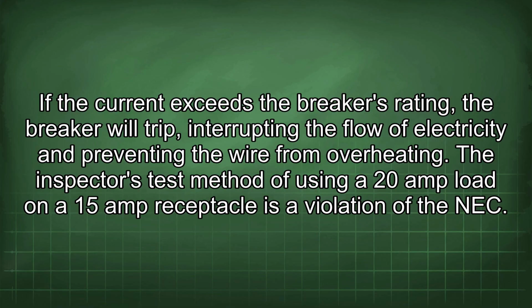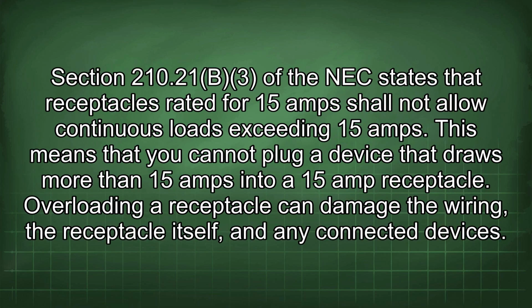The inspector's test method of using a 20 amp load on a 15 amp receptacle is a violation of the NEC. Section 210.21(B)(3) of the NEC states that receptacles rated for 15 amps shall not allow continuous loads exceeding 15 amps. This means that you cannot plug a device that draws more than 15 amps into a 15 amp receptacle.